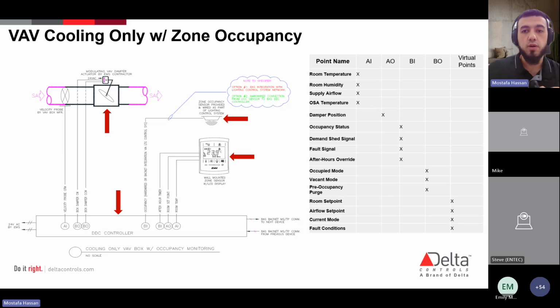Next up, your zone occupancy and vacancy will be actively monitored by connection to the lighting control system. Okay, so you have a zone occupancy sensor, which will allow the VAV to allow air in or to ramp up its CFM based on whether anyone is entering the room or not. If nobody's using the space, then the damper will close. And we'll see that a little bit. Actually, we'll see that right here in the next step.